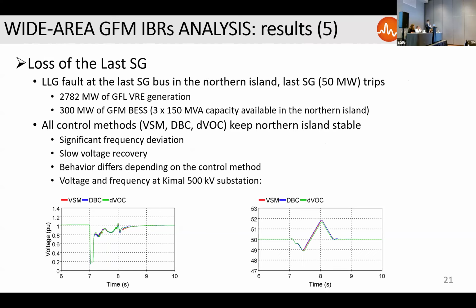The next test that was performed is the loss of last synchronous generator. So basically, it's the same test as previous. We have the island, but on top of it, we also disconnect the last synchronous generator. And now we can see that the recovery process is much more difficult. It takes more time, and the deviations of the frequency and voltage are much larger. So if you take a look at the figure on the left, you can see that it takes much longer, and the deviations are much worse than in the previous case. However, at the end of the day, we still go back to stable operation.